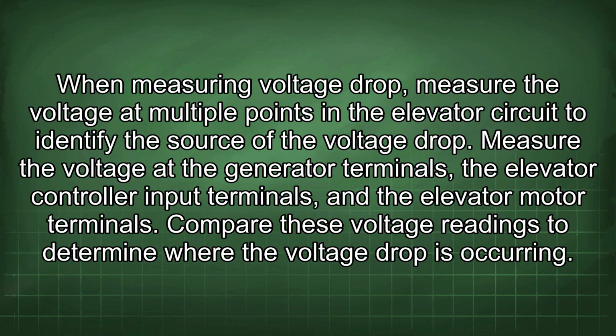When measuring voltage drop, measure the voltage at multiple points in the elevator circuit to identify the source of the voltage drop. Measure the voltage at the generator terminals, the elevator controller input terminals, and the elevator motor terminals. Compare these voltage readings to determine where the voltage drop is occurring.